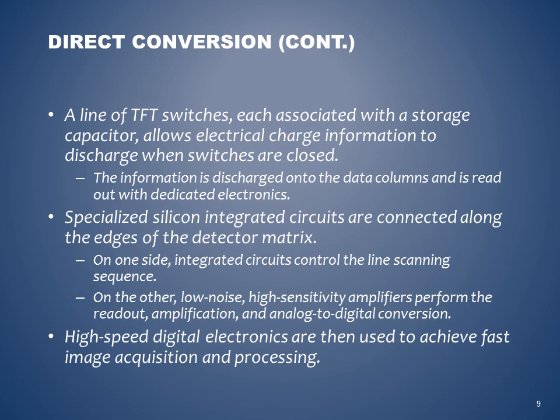A line of TFT switches, each associated with a storage capacitor, allows electronic charge information to discharge when switches are closed. The information is discharged onto the data columns and is read out with dedicated electronics. Specialized silicon integrated circuits are connected along the edges of the detector matrix. On one side, integrated circuits control the line scanning sequence. On the other, low-noise, high-sensitivity amplifiers perform the readout, amplification, and the analog-to-digital conversion. High-speed digital electronics are then used to achieve fast image acquisition and processing.